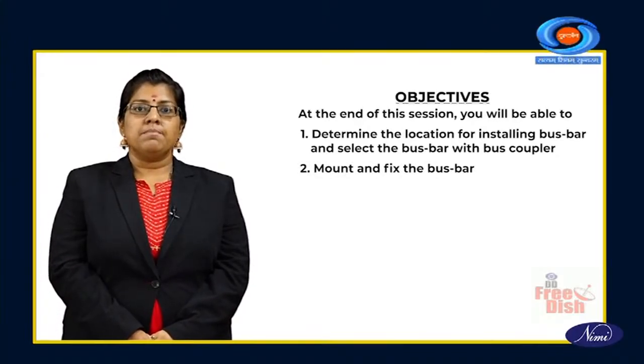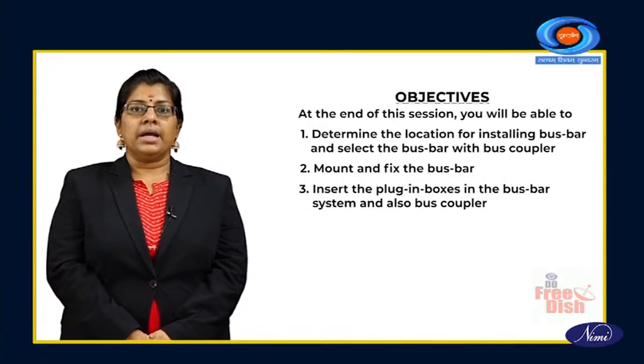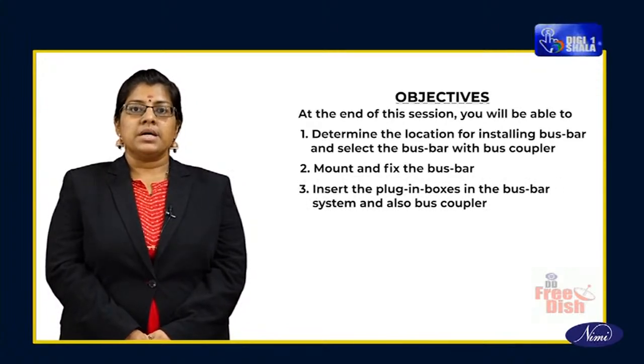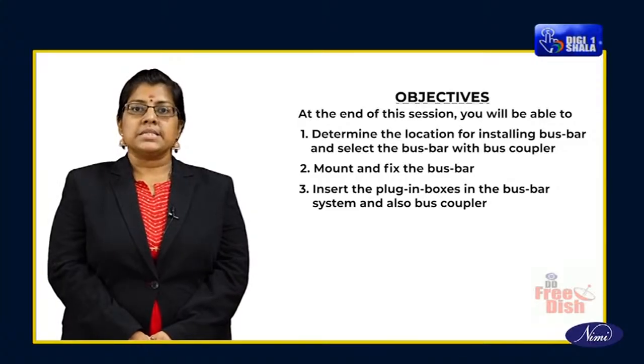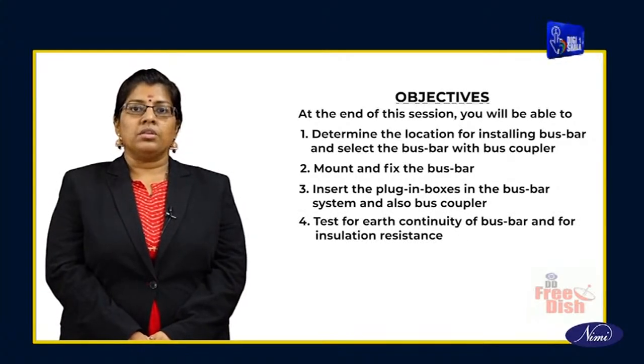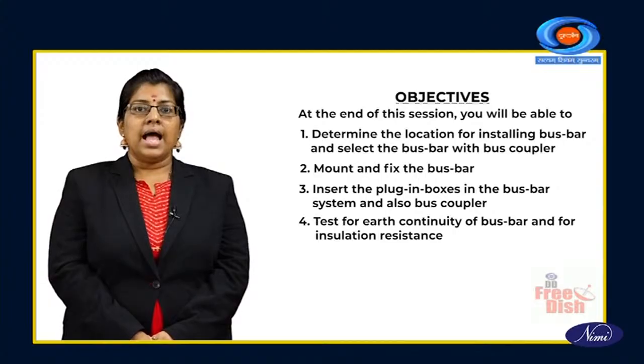Mount and fix the bus bar. Insert the plug-in boxes in the bus bar system and also bus coupler. Test for earth continuity of bus bar and for insulation resistance.